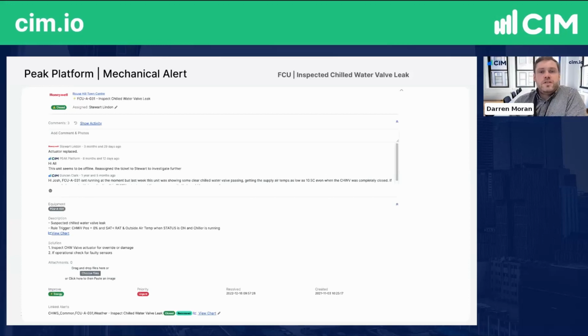So here we have an alert generated with the fan coil unit. Our software has identified an issue with the valve which controls the cooling. Our software gives a detailed description on the issue and the rule that triggered the alert. But not only does it give you a detailed description, it also gives you a list of detailed solutions from the most probable to the least probable, so that your on-site team have a step-by-step guide on how to rectify the issue.